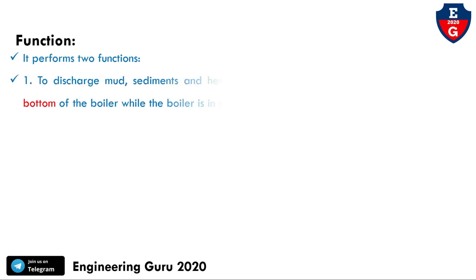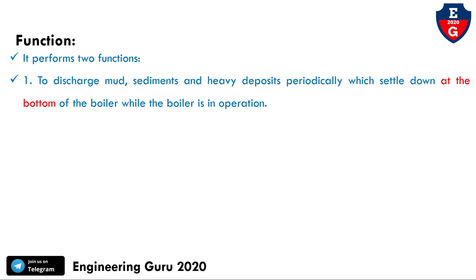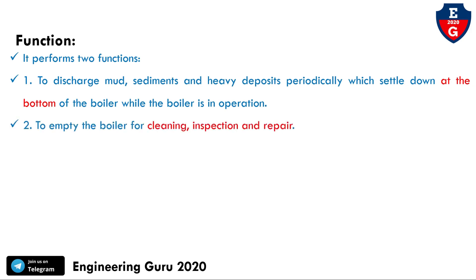Now we will see the function of this cock. It performs two functions. First, to discharge mud, sandy deposits and heavy sediments periodically that settle down at the bottom of the boiler while the boiler is in operation. Second, to empty the boiler for cleaning, inspection and repair.